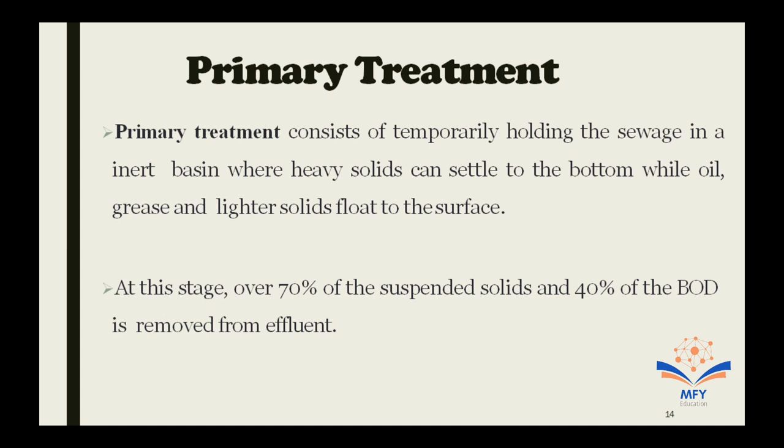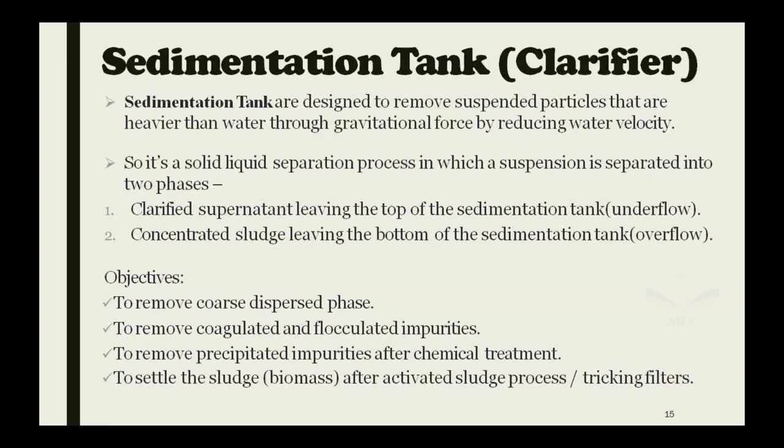Primary treatment can be either only physical or can be combined with chemical methods depending upon the effluent characteristics. At this stage, over 70% of the suspended solids and 40% of the BOD is removed from the effluent.